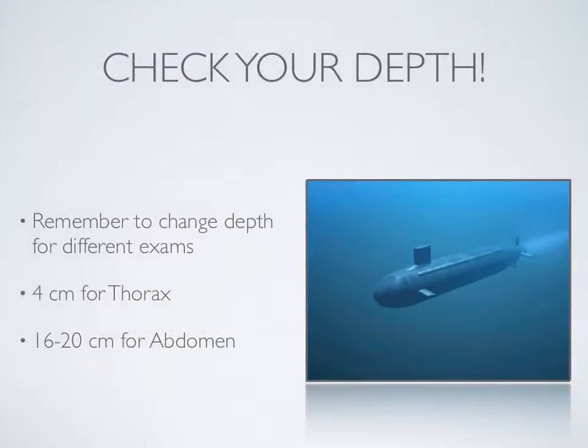Finally, check your depth. Remember that there's a depth number that you can toggle on your machine that allows you to see upwards of 26 or almost 30 centimeters in an abdominal exam mode, or 4 to 6 centimeters when you're doing a linear probe exam. When you're looking at the thorax, set it down to about 4 centimeters. When you're looking in the abdomen, set it to about 16 to 20. Really, this varies based on the patient's body habitus, but most patients will be fine with about 18 centimeters, even some of the bigger ones.